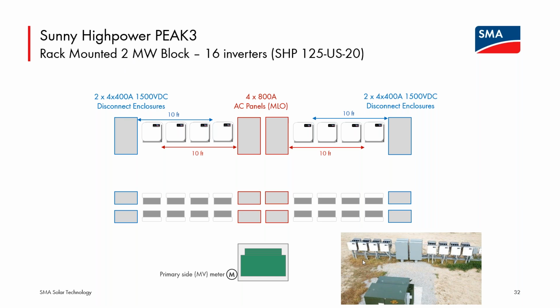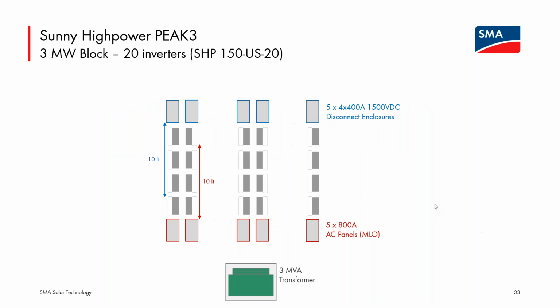So an exciting device, again, really aimed at a different market segment than the CORE1, but a common off-the-shelf inverter to scale up to very, very large megawatt plant size for these ground mounts. And a few other options, again, using the 150 kilowatt inverters gets you that 3 megawatt plant size. So similar layout, with DC and AC disconnect in the racks or rows of potentially back-to-back inverters, with your transformer close by.